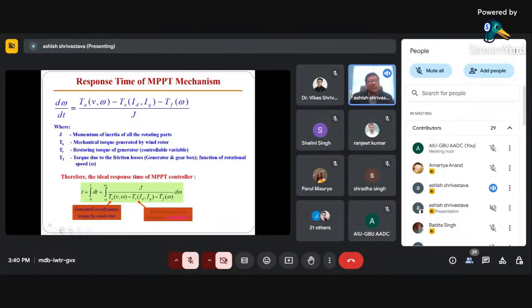If you want to calculate the time, you just have to get dt on the other side, cross multiply the other factor, and integrate. So you will get the ideal response time of the MPPT controller. Because whenever we design the MPPT controller, this is the time, from 0 to 2 dt, and that will be omega 1 to omega 2 for the particular variation of the speed. If these factors are well known to you, you can calculate how much time, with the change in the speed, your maximum power point tracking should take to trace again as per your controller design. So that is how much time.